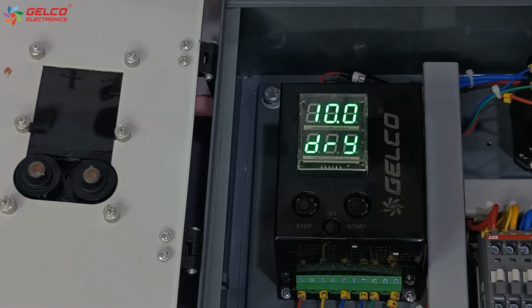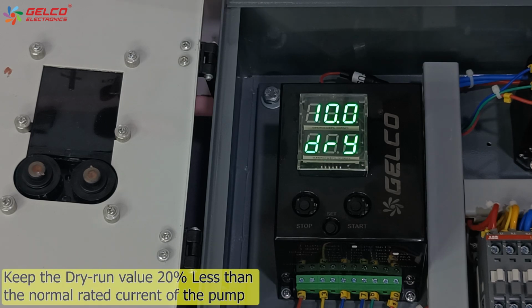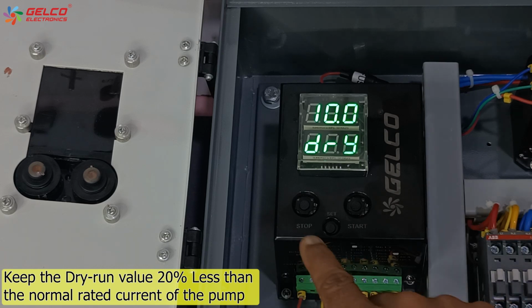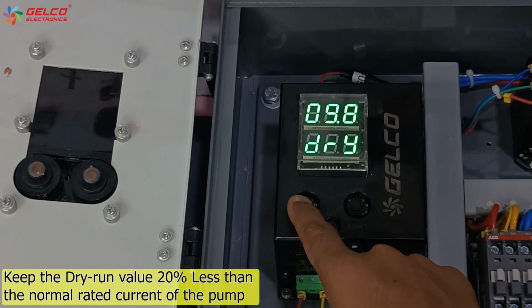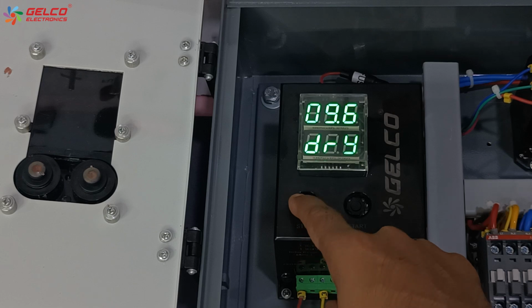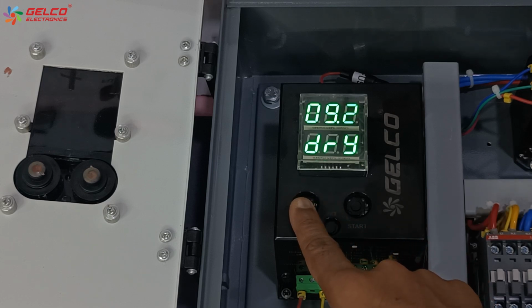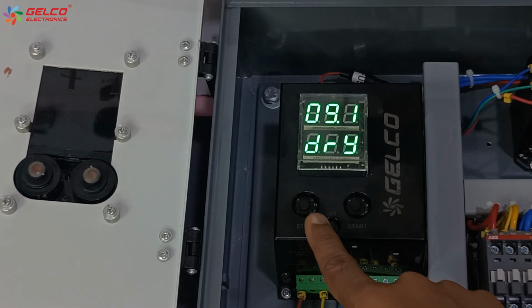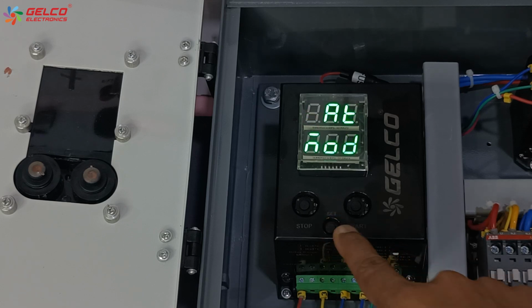Now Dryrun option will appear on the panel's display. The value of dry run protection should be set 20% less than the normal rated current of the pump. So we will set the dry run value to 9.1. Press the set button after the value is set.